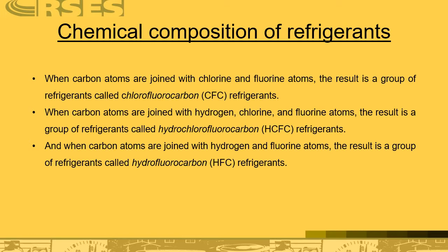So basically your CFCs are gone. HCFCs are pretty much being phased out as we speak. There are still refrigerants in stock for replacement use only, and not for new equipment. And HFC refrigerants are going to start being restricted next year in new equipment, with more refrigerants coming down the pipeline. More information to follow. Stay tuned.